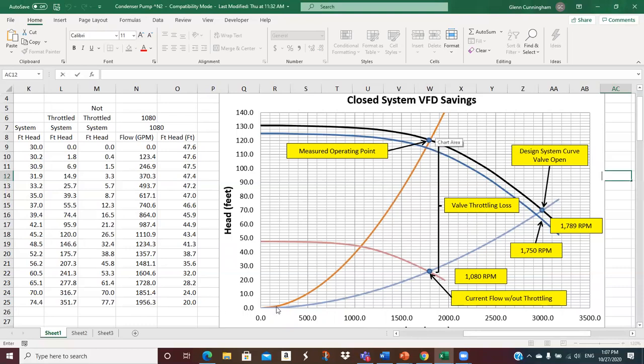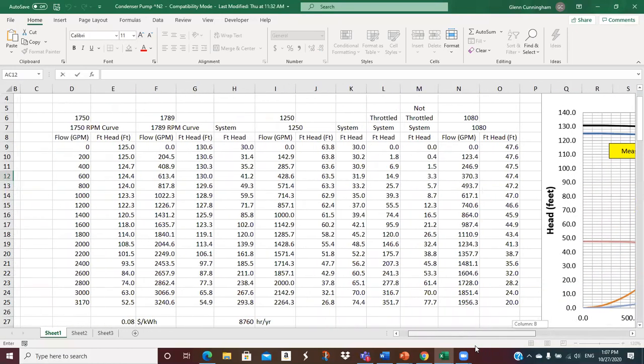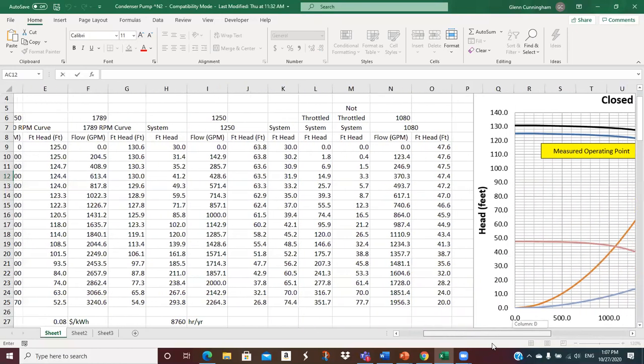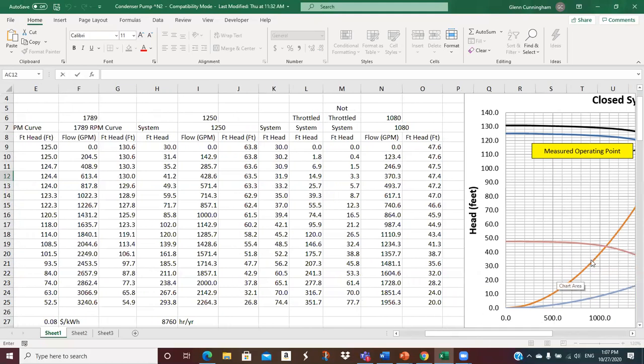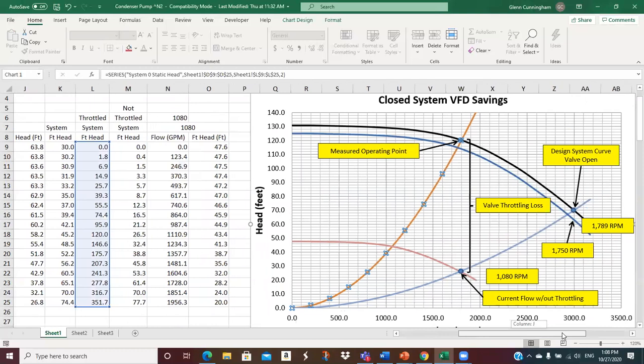So this was an all frictional system, didn't have static head. And so this is a measured flow rate and pump head. So, you know, it's easy. You go to PSAT, you do the math, and let's see. So let's see which curve is which. There you go. So this is the throttled system, because what these people were doing, they had a valve closed.